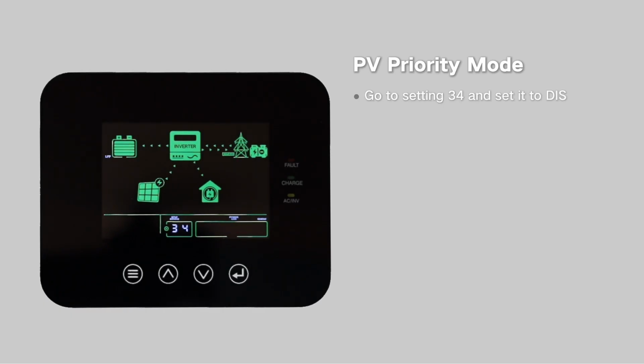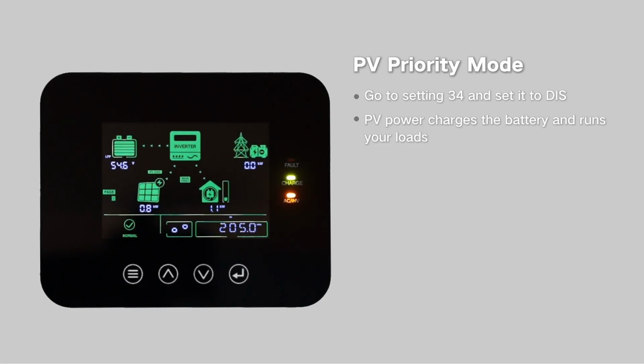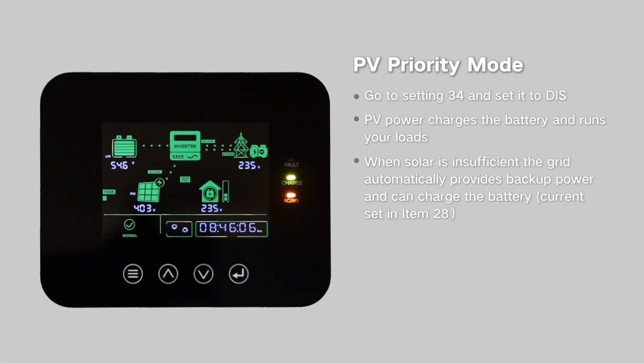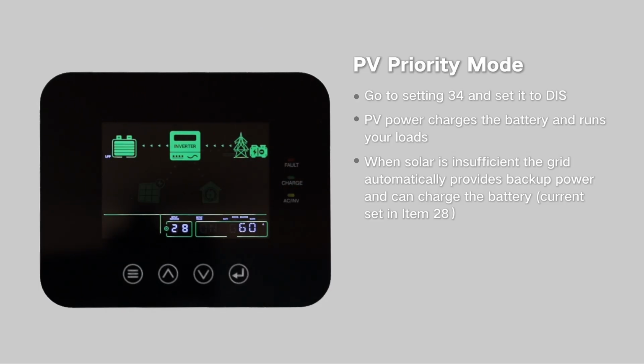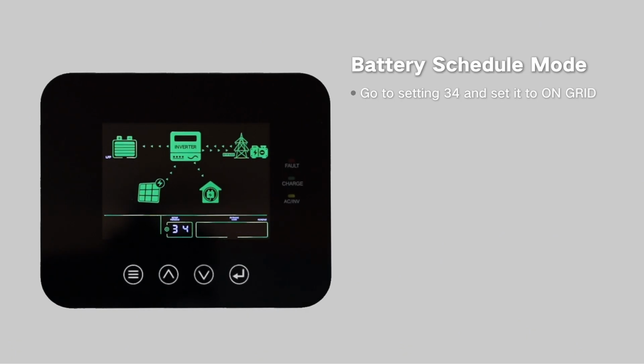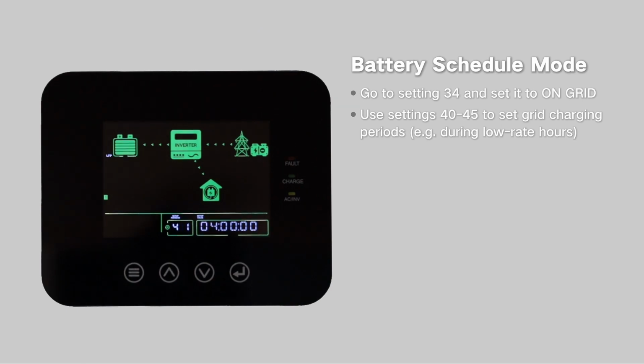Go to setting 34 and set it to DIS. PV power charges the battery and runs your loads. When solar is insufficient, the grid automatically provides backup power and can charge the battery. Current set in item 28. Battery schedule mode. Go to setting 34 and set it to on grid. Use settings 40 to 45 to set grid charging periods.